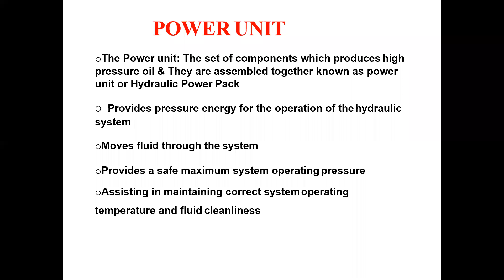The power unit is the set of components which produces high pressure oil. They are assembled together, known as power unit or hydraulic power pack. It is directly available in the market. You don't need to buy each and every component. The complete mountings are available in the market. They provide pressure energy for the operation of the hydraulic system. Moves fluid through the system. They also provide a safe maximum system operating pressure. It also assists in maintaining correct system operating temperature and fluid cleanliness. Then how they are going to achieve this, we will see during its function in the next slide.